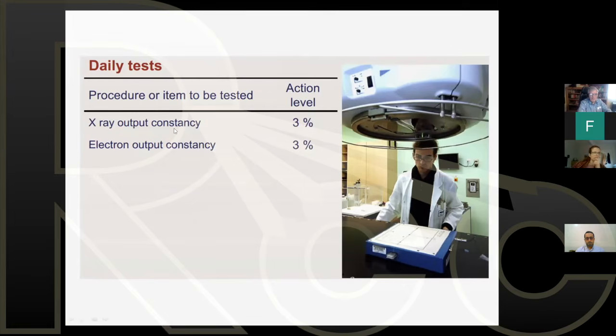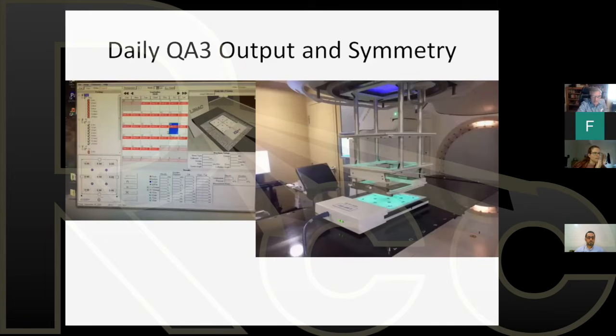On a daily basis, the X-ray output constancy and the electron output constancy, is it changing from day to day? Must be within 3%. That's the action level. There is a program software which looks at the device. So here's the QA3 device. And here it is set up in my clinic for an electron beam measurement of flatness, symmetry, and output. Now the numbers appear here, and if the numbers appear in red, that means it's failed. But if the numbers appear in green, then that means that it has passed for that day.